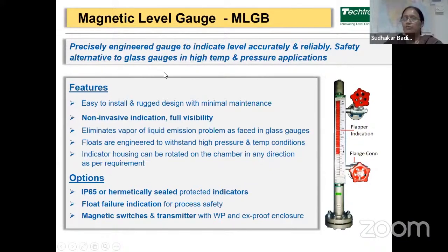It can be used as a safety alternative to glass gauge for high temperature and high pressure applications. This is easy to install, a rugged design with minimal maintenance. The indication is non-invasive and it will give you full visibility. It eliminates the vapor and liquid emission problem as we faced in the glass gauges. The floats used in this gauge are engineered to withstand high pressure and high temperature applications. The indicator housings are clamped on the chamber, and this indicator can be rotated on the chamber in any direction as per the requirement. Again, these indicators are available as IP65 or with hermetic sealing protection. The float failure indications are provided optionally for process safety.